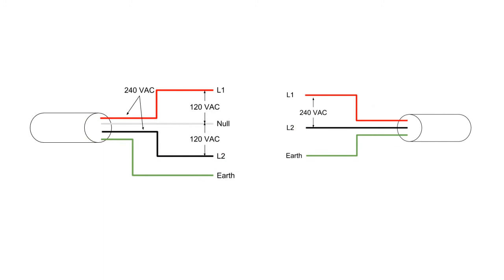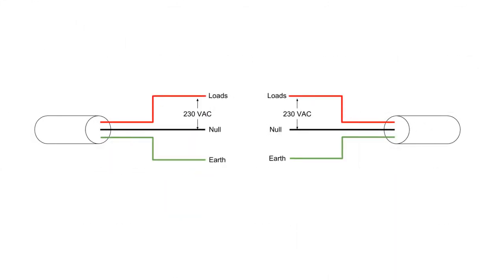Compared to the wires from the grid, there are only 3 wires coming from the inverter. In North America, the inverter wires are connected to L1, L2 in the panel through a breaker, and earth, which requires no breaker. There is no null wire, as the null voltage is handled by the electrical panel itself. In Europe, the 3 wires from the inverter are connected to load and null through a breaker and earth. A much simpler connection.